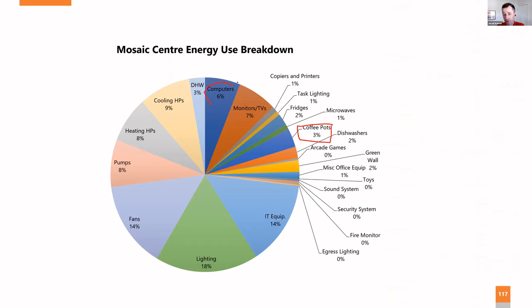But the key takeaway from commercial building, even in our cold climates, is that most commercial buildings are actually cooling dominant. And what I mean by that is that they actually spend more time and require more energy in cooling than heating. And that's because of, one, in our sunny climates, solar gains, because of gains from people, from lighting, computers, and equipment that are on for a large portion of the time, and especially interior space. If you think of an interior meeting room, which has no outside walls, it's basically cooling all of the time.